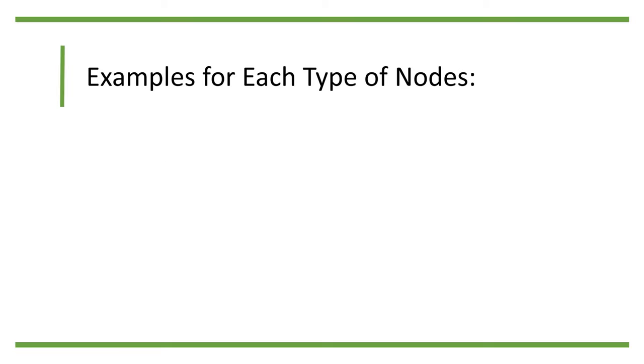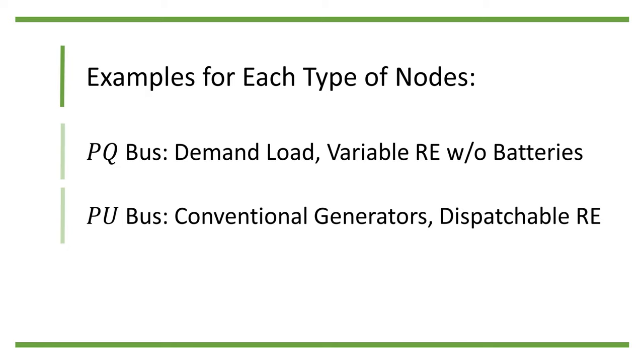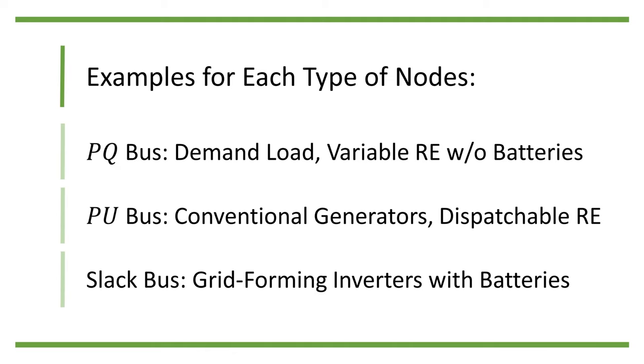Let's take a look at what are usually modeled by each type of nodes. We usually model demand nodes and variable renewable energy without batteries with PQ buses. Meanwhile, conventional generators and dispatchable renewable energy are usually modeled as PU buses. Finally, grid forming inverters with batteries are examples for slack buses.